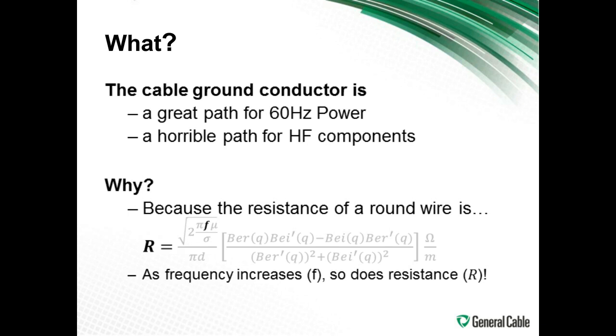It is not a good path for high frequency components because as the frequency goes up in this formula for resistance or impedance of the system, the wire's resistance goes up. When the resistance goes up, well, guess what? The current doesn't want to go in that path. It wants to take the path of least resistance. It's going to find an alternate path.